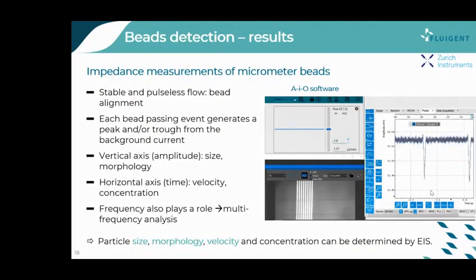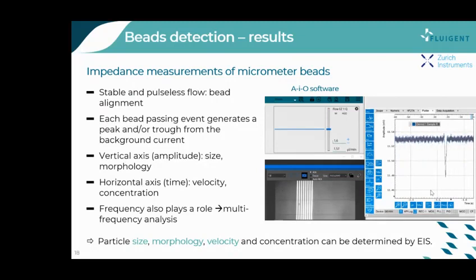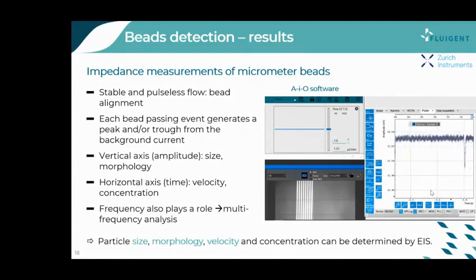So this is how the measurement looks like. On the right side of the slides, you can see the results from the bead detection. On the top left of the video, you can see Fluigent's software permitting to monitor and control both the flow rate and the pressure. The flow rate set at 1.6 microliters per minute is highly stable, allowing for experiments with very high reproducibility. On the bottom left, you can see the microbead solution passing through the chip's main channel containing the set of electrodes. Each bead passing event will lead to a change from the background current, shown here as either a peak or a trough.